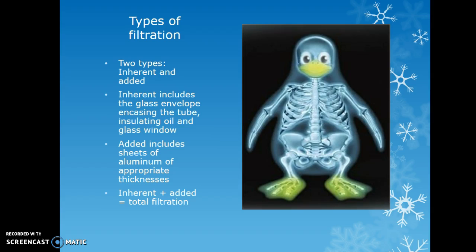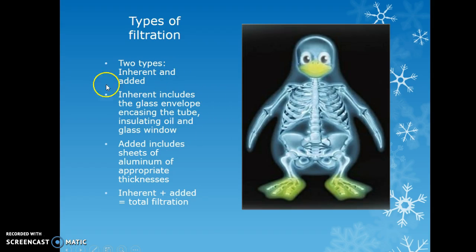There are two types of filtration: inherent and added. Inherent filtration includes the glass envelope, tube casing, insulating oil, and glass windows — all the physical parts before the collimating housing. Added filtration includes sheets of aluminum of appropriate thickness; some older tubes have an adjustable disc between the collimator housing and the x-ray tube. Inherent plus added equals total filtration.